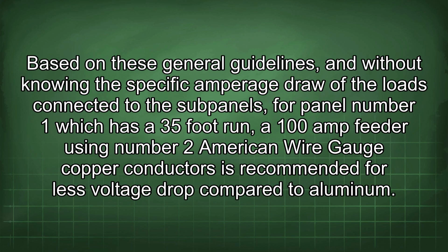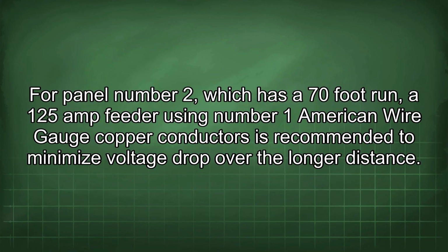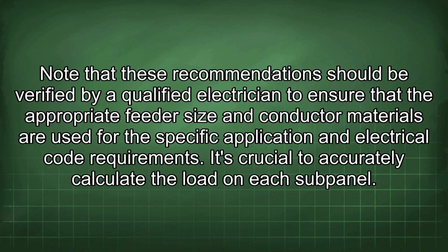Based on these general guidelines, and without knowing the specific amperage draw of the loads connected to the subpanels, for panel number 1, which has a 35-foot run, a 100 amp feeder using number 2 American wire gauge copper conductors is recommended for less voltage drop compared to aluminum. For panel number 2, which has a 70-foot run, a 125 amp feeder using number 1 American wire gauge copper conductors is recommended to minimize voltage drop over the longer distance. Note that these recommendations should be verified by a qualified electrician to ensure that the appropriate feeder size and conductor materials are used for the specific application and electrical code requirements.